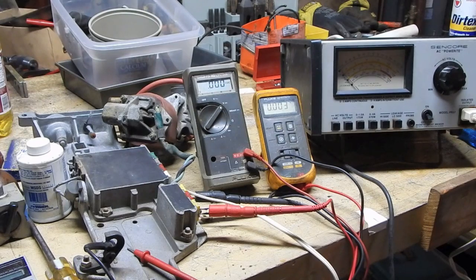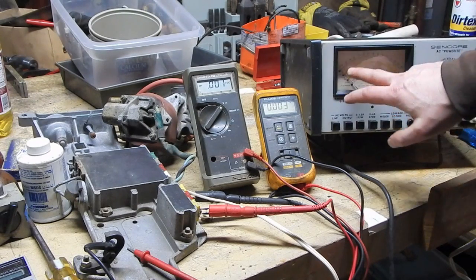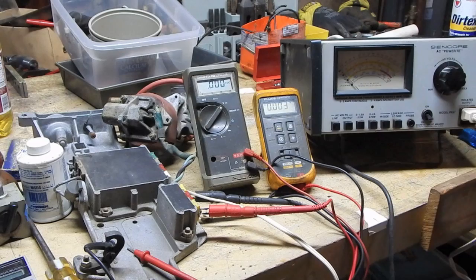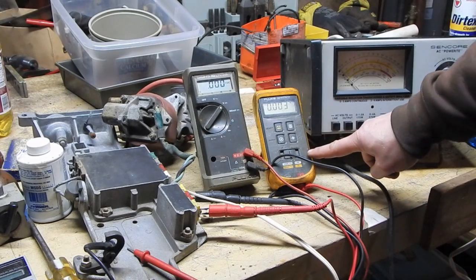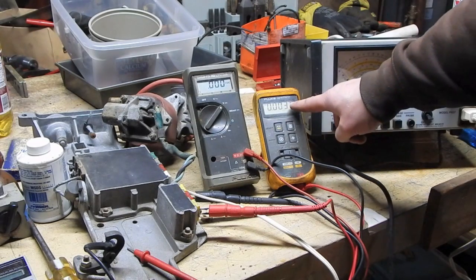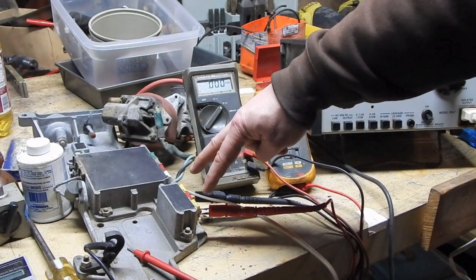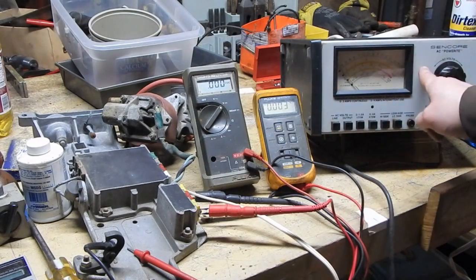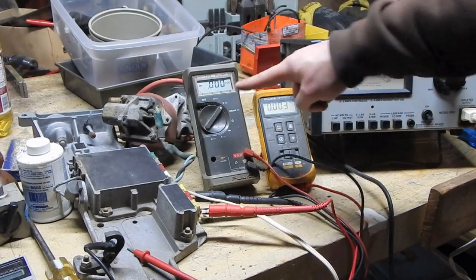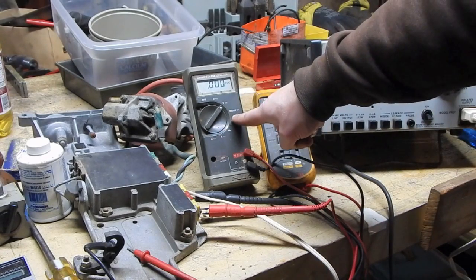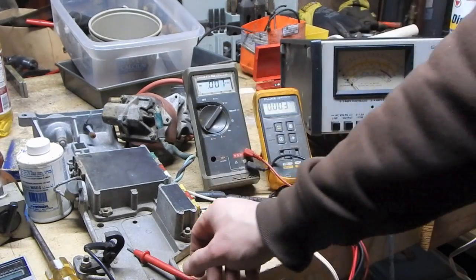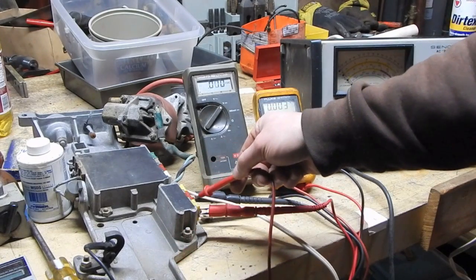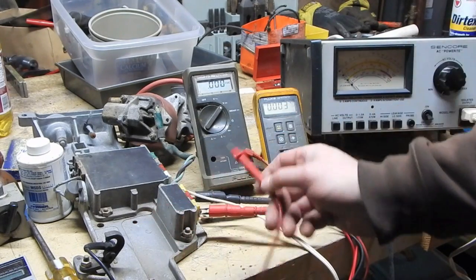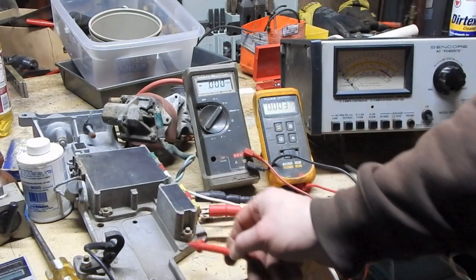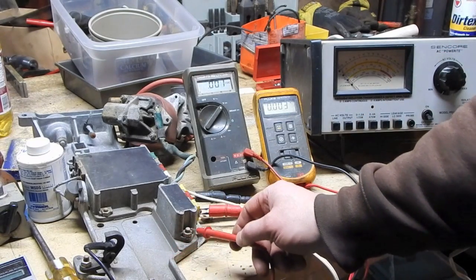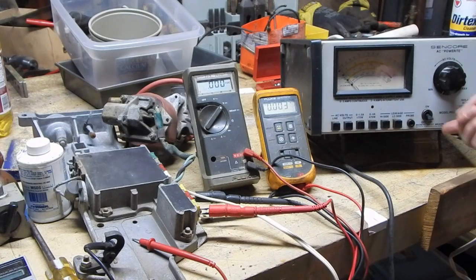Since I'm using this meter to monitor my current, I've hooked up my Fluke DVM set to AC volts across the input so I can monitor what's coming out of the variac and going in. Then I've got my other Fluke DVM set up for DC voltage, but I don't have the alligator clip, so I'm just going to hold this on here. The ground for the Fluke is the casing, since they're using the case as the ground path. Let's fire it up.